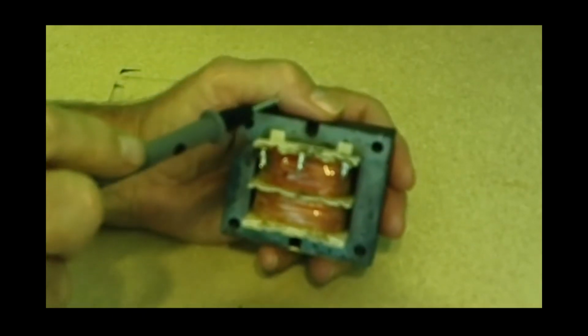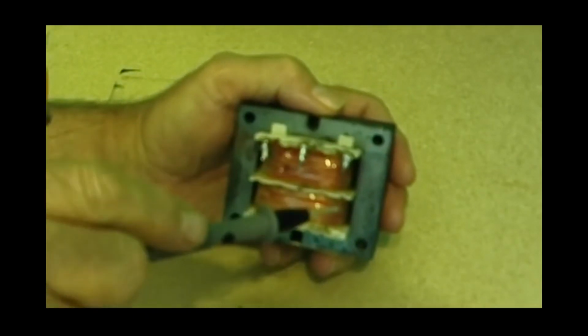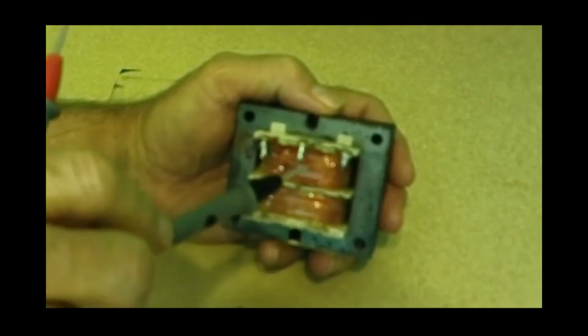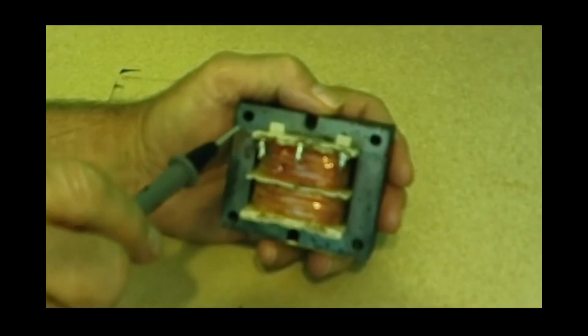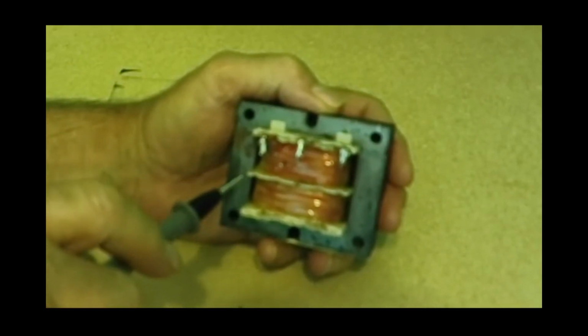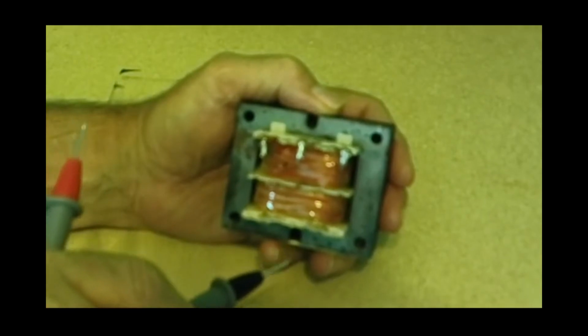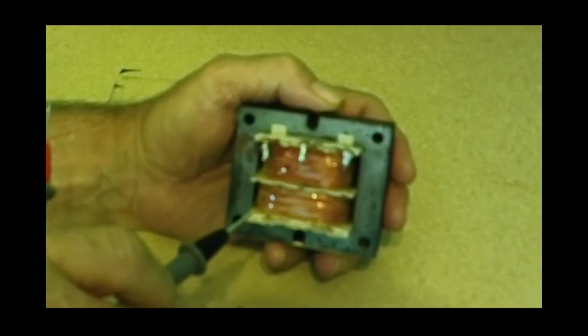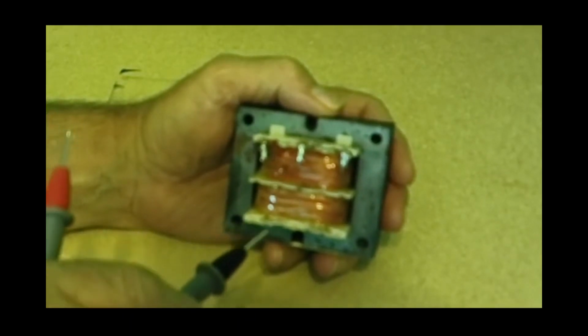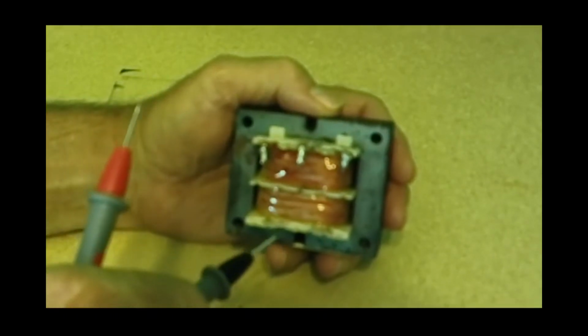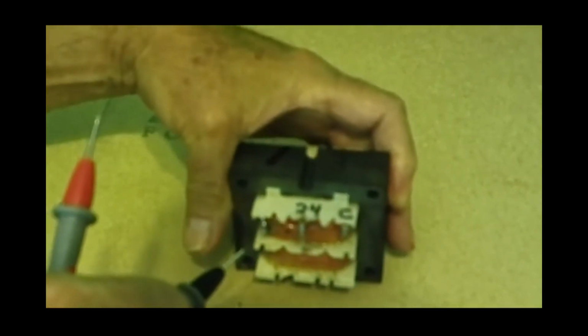If I have 100 volts on the primary and 20 volts on the secondary, we have a ratio, or a turns ratio, of 5 to 1. I will have 5 turns of wire on the primary side for every 1 turn of wire on the secondary side. That steps the voltage down. And the ratio would work backwards, stepping the voltage up. We'll get more into that shortly.